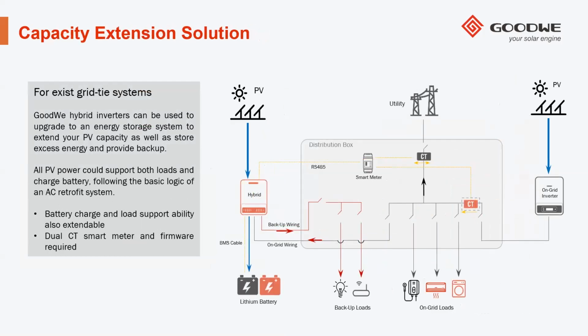So, capacity extension solutions. For existing grid-tie systems or existing storage systems, Goodwe hybrid inverters can be used to upgrade the energy storage system so that you've got hybrid backup as well. If you have an existing PV inverter over here, you can get a special smart meter with 2 CTs that's there to detect the production from the on-grid inverter as well as the consumption from the utility. With this data, if the inverter sees there is excess production from the grid-tie inverter that starts exporting to the grid, it will then consume that electricity and push it into your batteries.